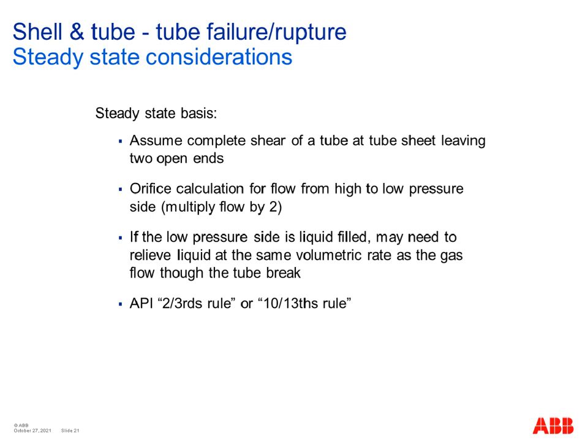You may be aware of the old API 2/3 rule, which is often talked about in industry, and this was based on the test pressure being 1.5 times the design. So the 1.5 is where the 3/2 comes from. The theory of this is that if the maximum pressure experienced by the low pressure side is lower than the test pressure, then catastrophic failure is unlikely and the case can be ignored. So if the low pressure side test pressure is actually greater than the HP side design pressure, then catastrophic failure is unlikely because the LP side will be good for that. So this principle is still in place, this 2/3 rule.